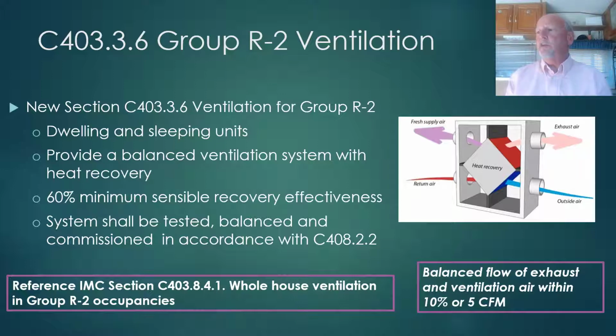This term balanced flow just means that the exhaust and ventilation airflows are within 10% of each other. We don't want to generate a large pressure differential between the conditioned space and the exterior environment, or within 5 CFM. So we have balanced, relatively neutral pressure relationships between the interior and exterior environment.